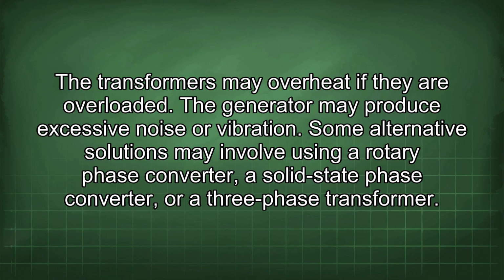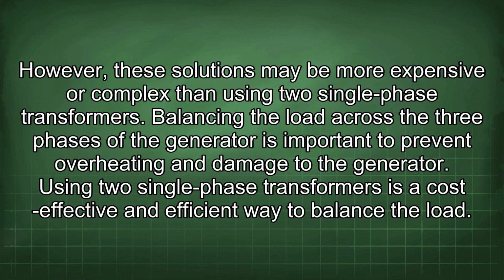Some alternative solutions may involve using a rotary phase converter, a solid-state phase converter, or a three-phase transformer. However, these solutions may be more expensive or complex than using two single-phase transformers. Balancing the load across the three phases of the generator is important to prevent overheating and damage to the generator. Using two single-phase transformers is a cost-effective and efficient way to balance the load.